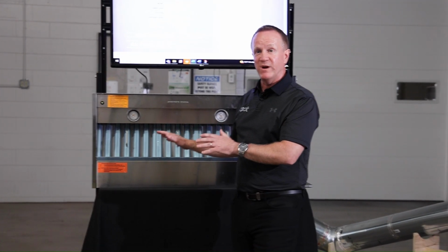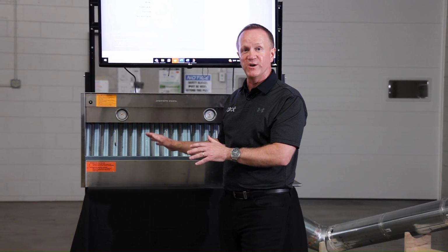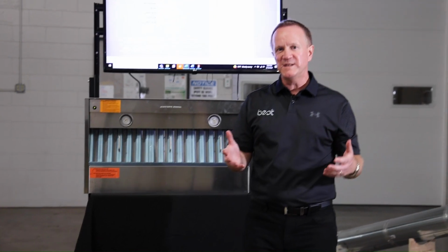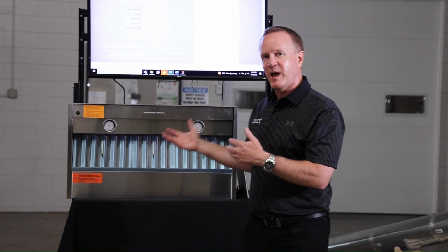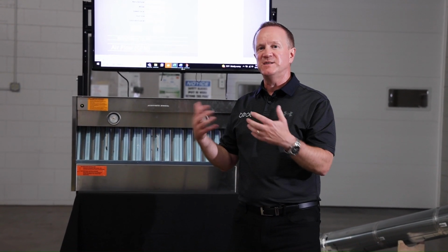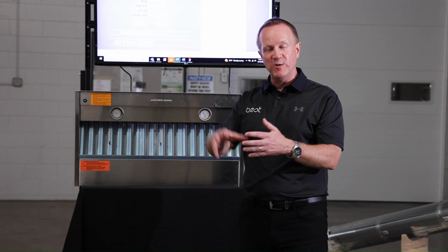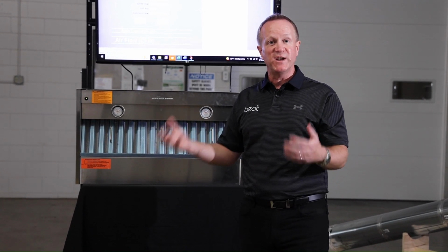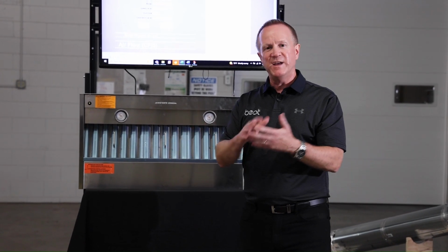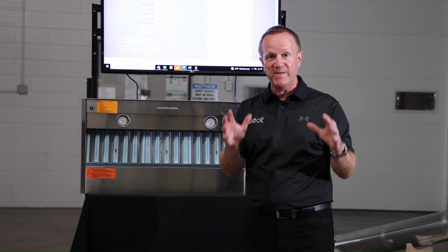And if I did that right, the hood is going to start to run. And I can hear that now it is starting to run. So what is the calibration process? What happens during calibration is that the hood is measuring the amount of back pressure that's generated by the ducting run. It's specific to any specific duct run.